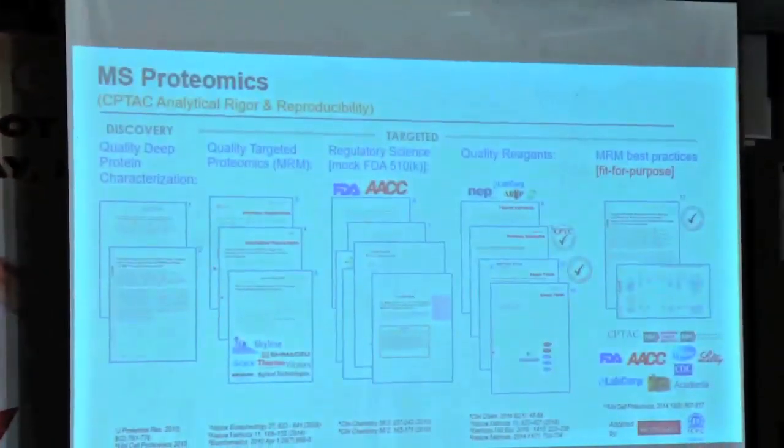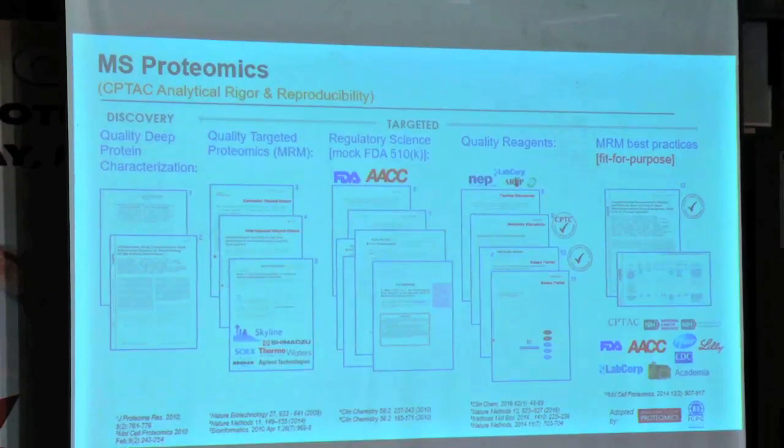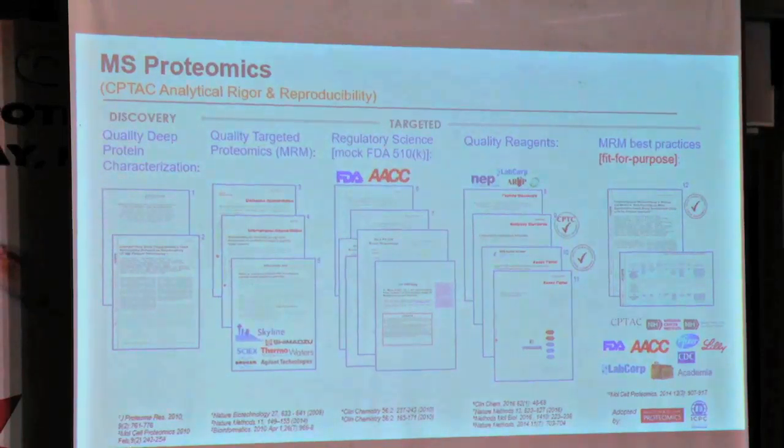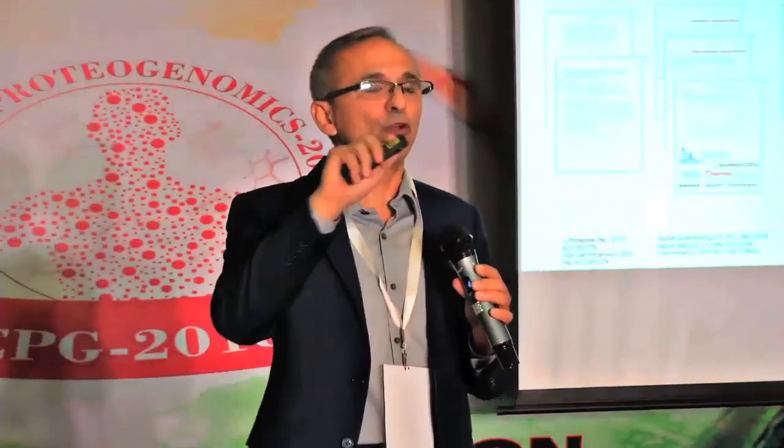We worked with the regulatory agency and clinical chemistry community in the United States. Typically, manufacturers submit a 510K to the FDA, which marks up the document with comments and concerns, but companies never release it to the public. We decided to make it very transparent. We held a workshop and submitted an official filing with the regulatory agency using this measurement technique. Because we used fabricated data but did not make up our analytical workflows, it allowed the FDA to mark up the document. Once we got the documents back, we published all their markings, making very transparent the type of questions you would face when submitting an instrument for these measurement techniques for FDA approval.